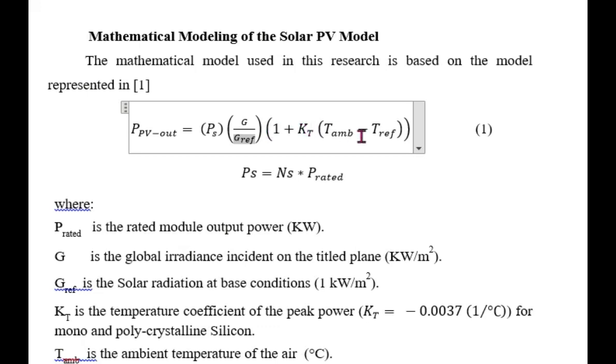1 plus KT, T ambient is the ambient temperature of that location. This is the T reference, for which the rating of that solar panel power is given. KT here is the temperature coefficient of the peak power, for mono or polycrystalline.